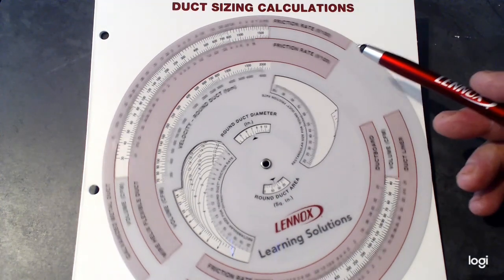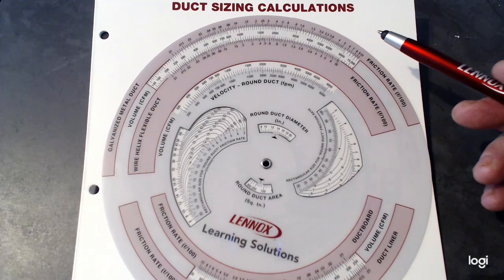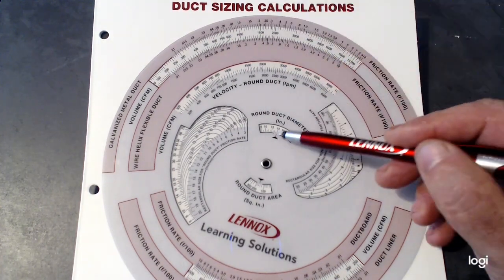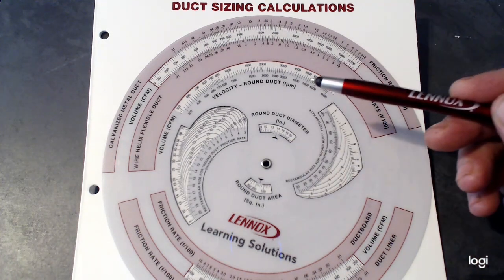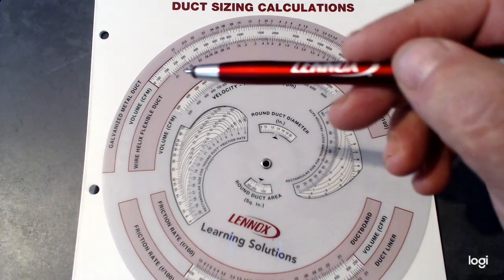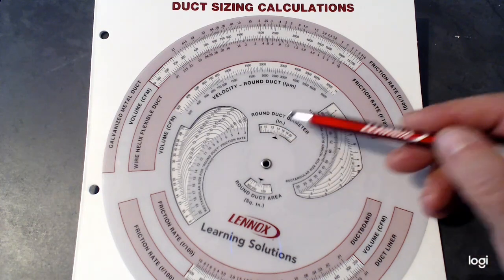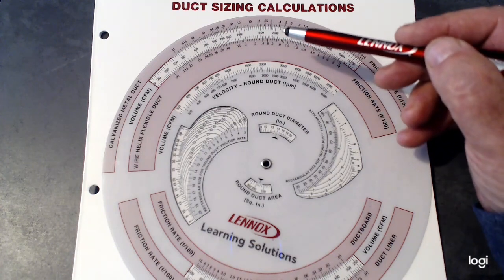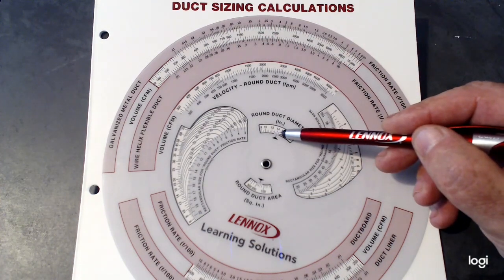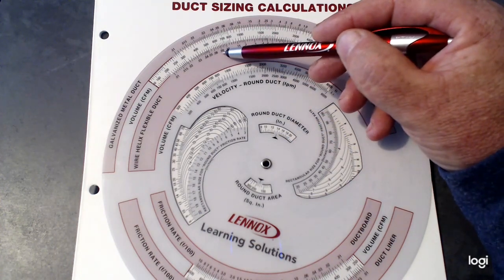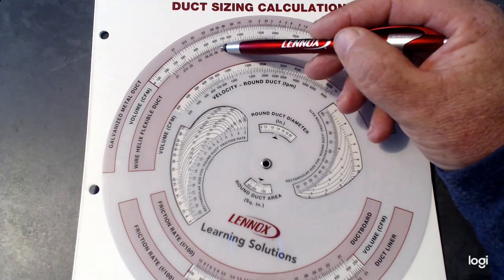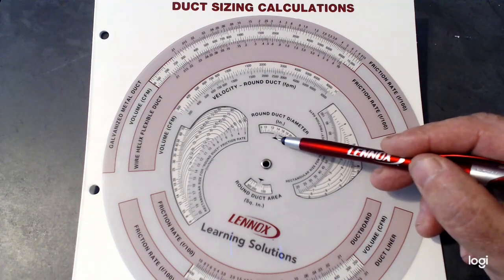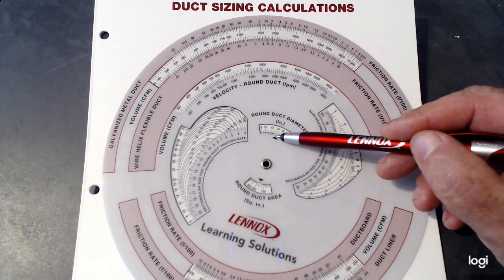Now let's go to a popular number — 14-inch round — popular because there are a lot of 14-inch returns out there. When you take out an R-22 system and put in a 410A, it often has a 14-inch duct. If we use a 0.06 or 0.08 friction rate number for 14-inch flex, we come up to somewhere around 650 CFM. So obviously, that's not enough for a three-ton system. This is how you use the round duct portion of the calculator.